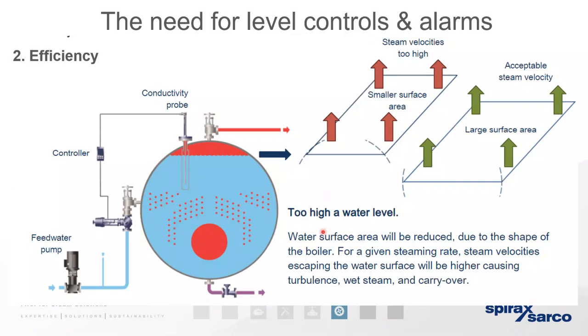As it shows here, if you have a water level that's too high, the space available for steam is much smaller, so the surface area to steam off is smaller. So we try to maintain this level at a fixed point, not too high but also not too low. This means we get the best quality steam. So we avoid erosion, corrosion, water hammering in your pipes, and inefficiency because the steam has less energy when it's wetter.